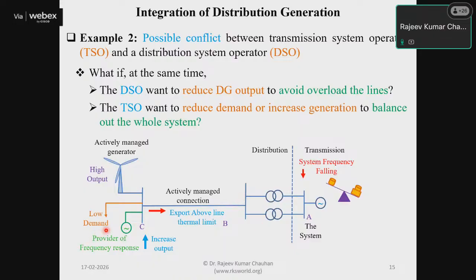The export line thermal limit will be the constraint here. Then the output at that particular location can be increased, if the limit allows, so just increase it further and start feeding it to the grid. And if this is not possible, then keep your system stable, and the rest of the things need to be taken care of by the utility.